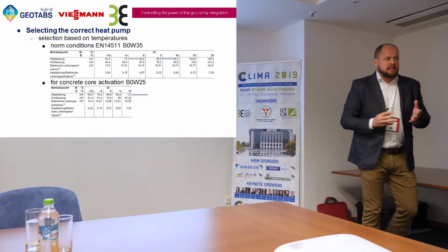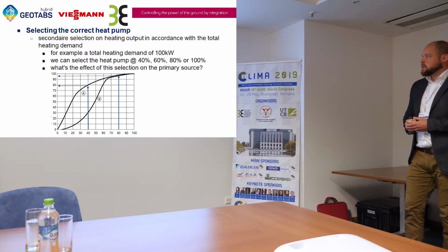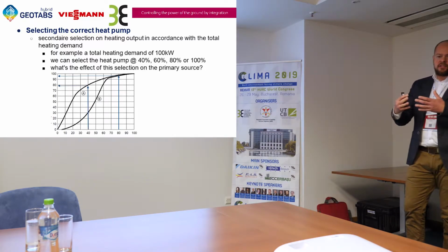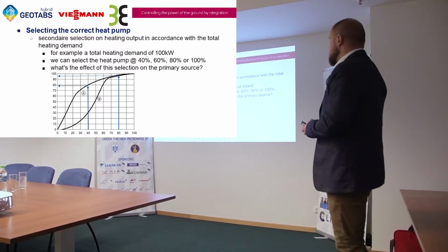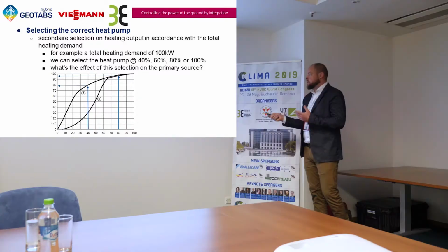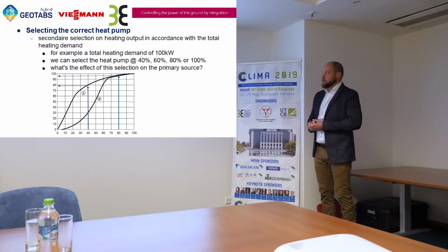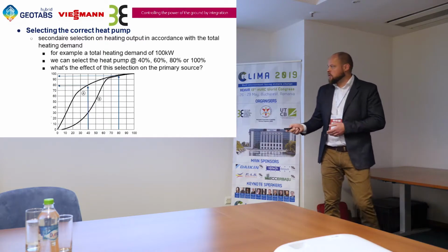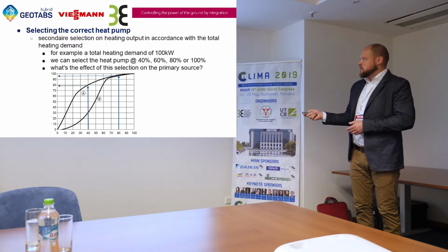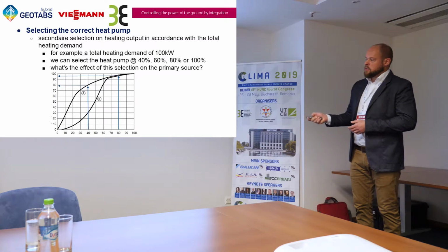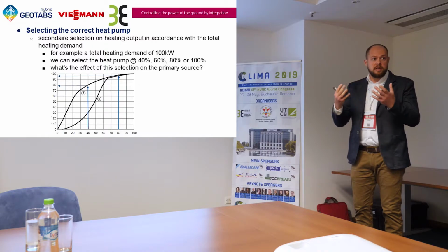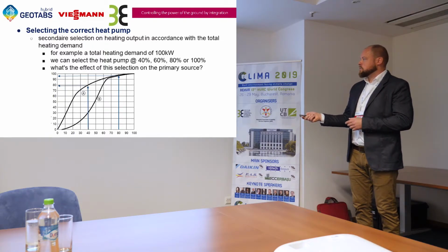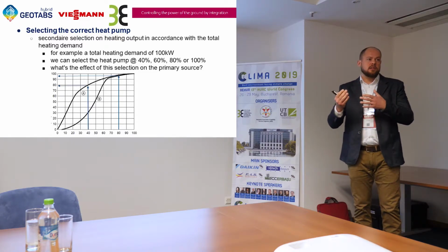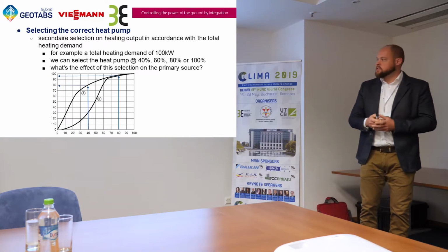Now, another aspect of selecting the heat pump, especially in a hybrid system, is that we can select the heat pump not at 100% of the demanded power. You can select, for example, the heat pump at 40%, 60, 80 or 100% of the total power. What does that mean in running hours, and what's the effect of this selection on the primary source? Therefore, we have a curve, you can see it here. This one is the parallel working curve, so it means that the gas boiler and the heat pump work together. This is the alternative curve. This means that when the gas boiler starts to work, the heat pump will stop working. There are the two differences you can see here.